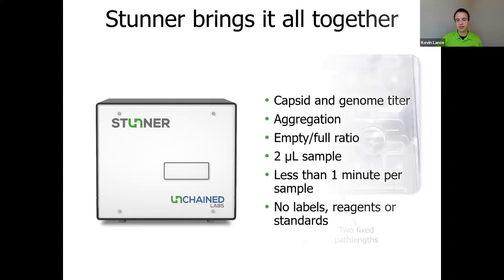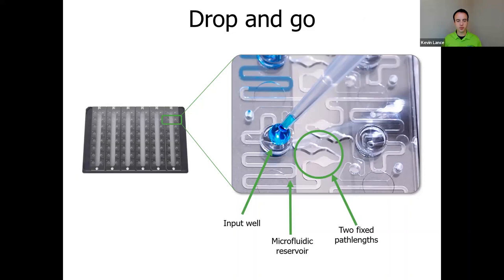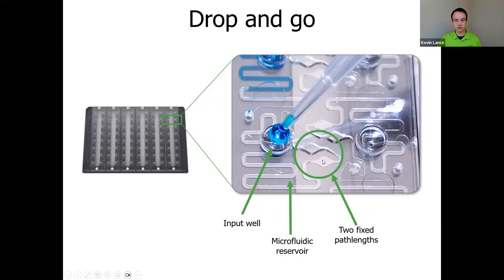Let's take a look at how this is done. Stunner operates using a Stunner plate, which follows a normal 8×12, 96-well plate SBS format. But instead of having an open cylinder, each one of those wells is a microfluidic circuit. That's where we take advantage of the two-microliter sample volume — we pipette our two-microliter sample into the input well. At the bottom of the input well is a tiny hole that allows the sample to be drawn into the serpentine microfluidic reservoir, where it hangs out until it's analyzed inside chambers that have two fixed path lengths: 0.1 mm and 0.7 mm.